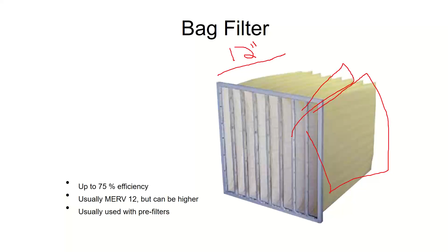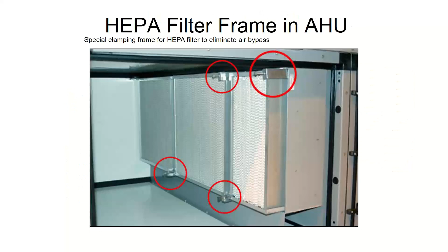So on really important jobs, you'll start having cartridges with very hard cardboard, or in this case metal, cartridges. That way I can put them very close to each other and even caulk in between them to make sure there's no leakage past them. HEPA filters are always going to be like that, because I can't have any bypass. They're so restrictive from a pressure drop standpoint that all the airflow has to go through them. So we'll caulk them and seal them up.